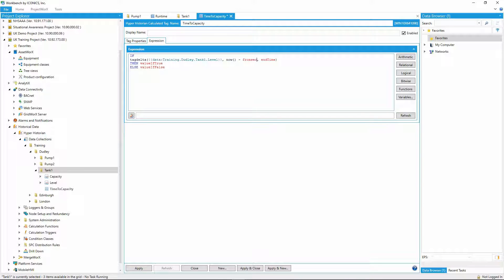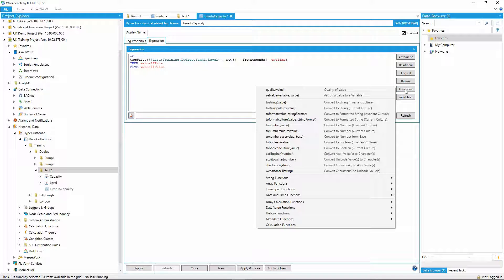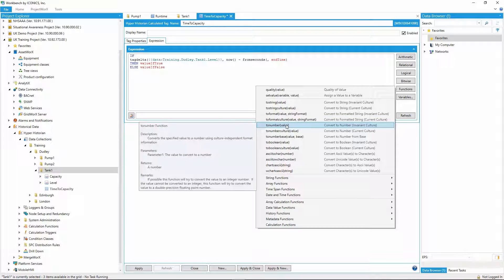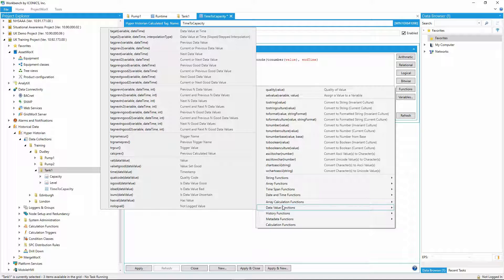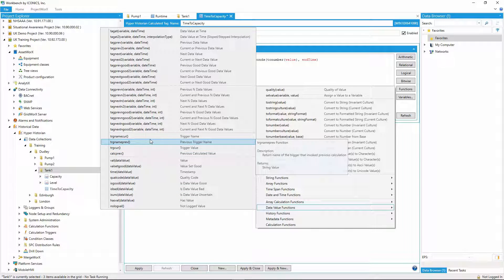I could put a value of 30 in here, since the calculation is triggered every 30 seconds, but to make it a little more flexible, I'll use the name of the trigger to determine the offset. This means that if I later change the trigger, the calculation will automatically adjust.